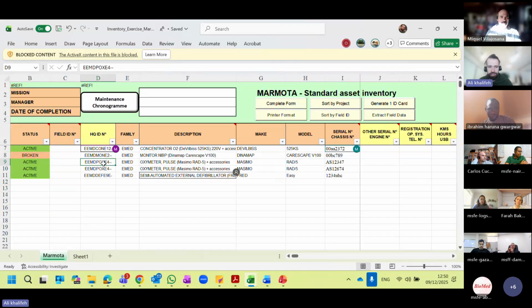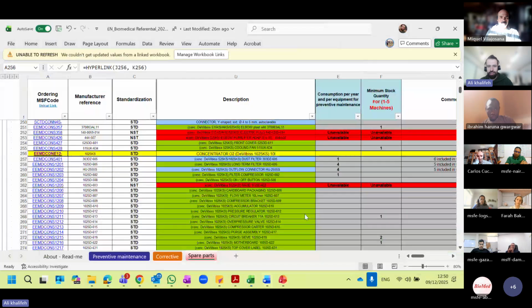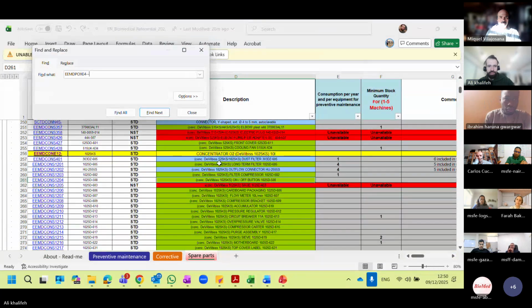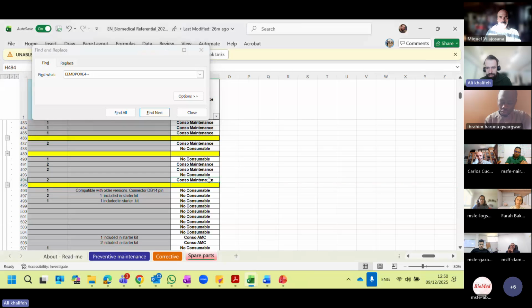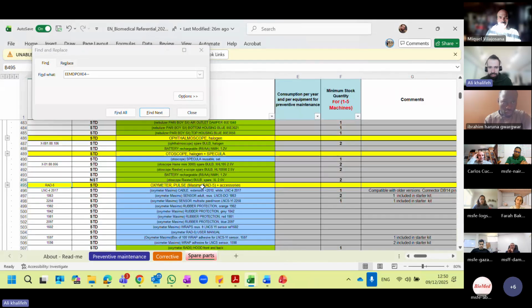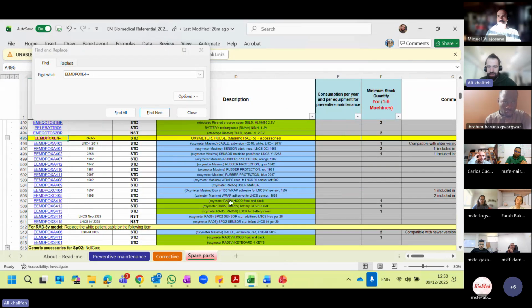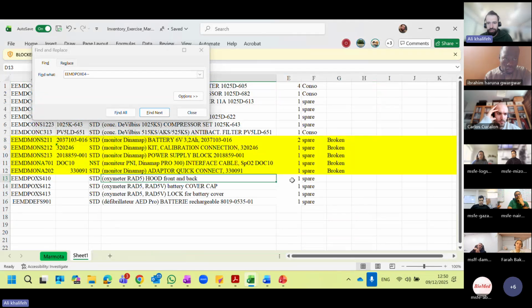For the oximeter, we did the same. We have 2 oximeters in our inventory. So when we go to the referential here, we can see that we have 2. Okay. This is the pulse oximeter. This is the spare part for logistics. We have 3. And the recommendation is to have 1 of this part, front and back cover, battery cover, and lock for battery, for every 1 to 5 machines. As we have 2 machines, we ordered in our list 1 item for each. Okay. They are all spare parts.